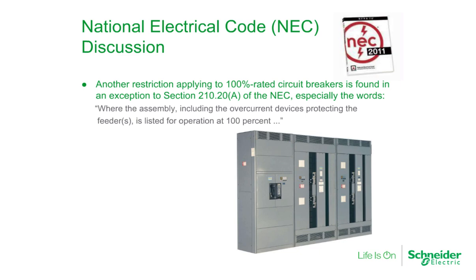Another restriction applying to 100% rated circuit breakers can be found in the National Electrical Code. The code states where the assembly, including the overcurrent devices protecting the feeders, is listed for operation at 100%. This says it is not just the circuit breaker that must be 100% rated — rather, the entire installation must be suitable for 100% operation.